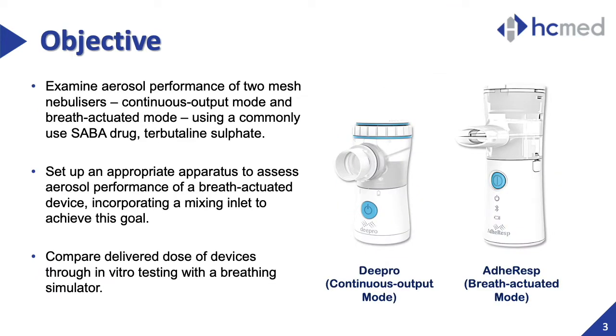Our study focused on three objectives. First, we aim to examine the aerodynamic particle size distribution of a continuous output mode mesh nebulizer and another operating under breath-actuation by nebulizing terbutaline sulphate, a commonly used SABA formulation. Second, we set up an appropriate apparatus for the testing of the breath-actuated device, incorporating a mixing inlet into the APSD testing system. Last but not least, we compared the delivered-dose performance of the two devices using a breathing simulator to investigate the benefits of breath-actuation.